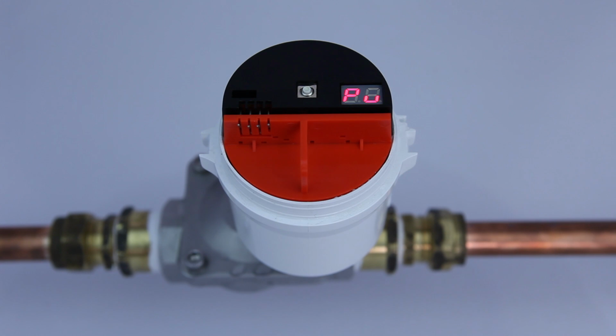So for example, half a litre per pulse, or 5 litres per pulse, or 10 litres per pulse, and so on. PU stands for pump mode. This mode must be enabled if you're fitting the AquaTrip to a pumped water supply that does not utilize a header pressure vessel, i.e. no air tank on the pump. Press and hold the button to change between yes or no. On some pump supplies, it may be necessary to put a backflow valve to prevent backflow and pressure variations interfering with the AquaTrip flow sensor.